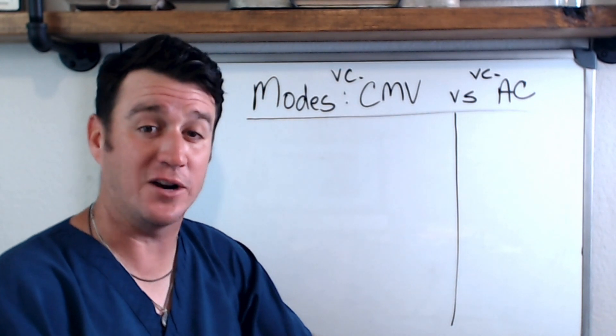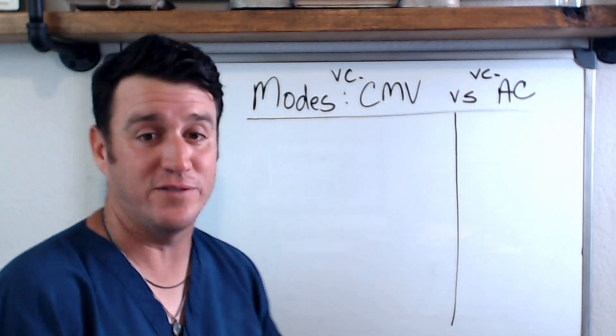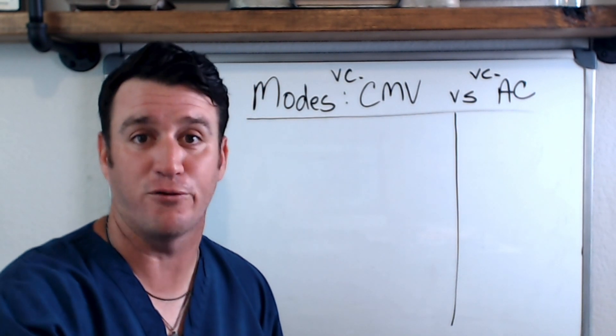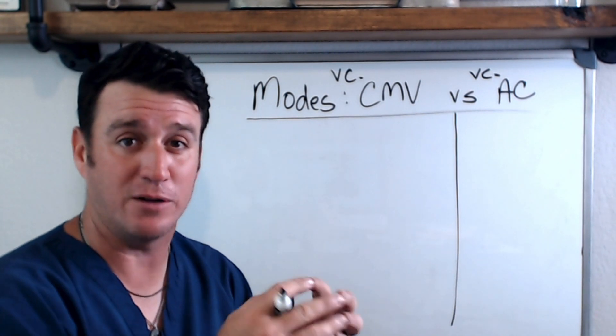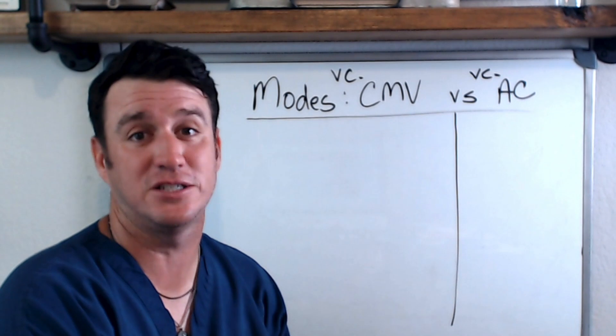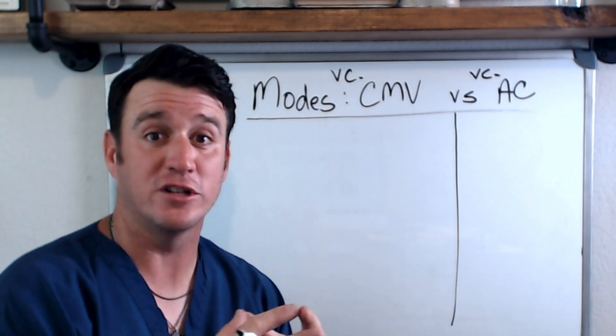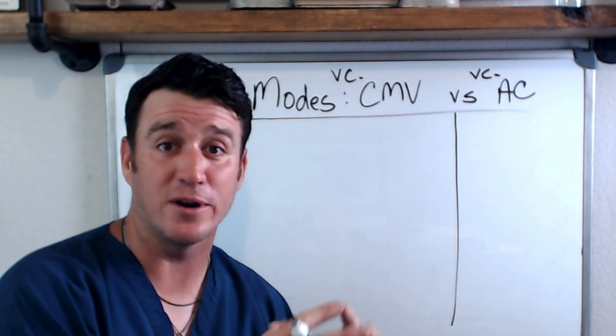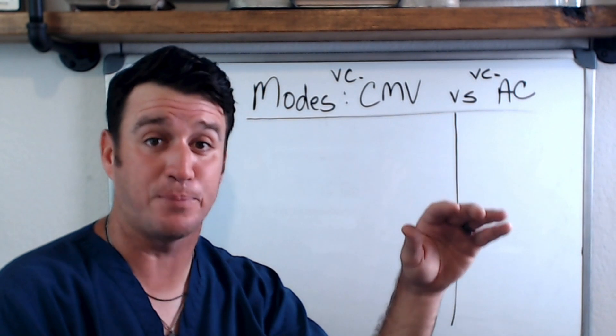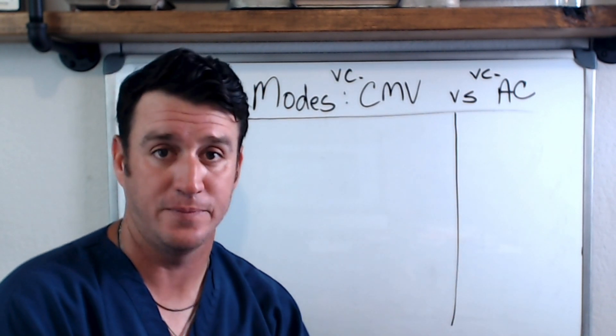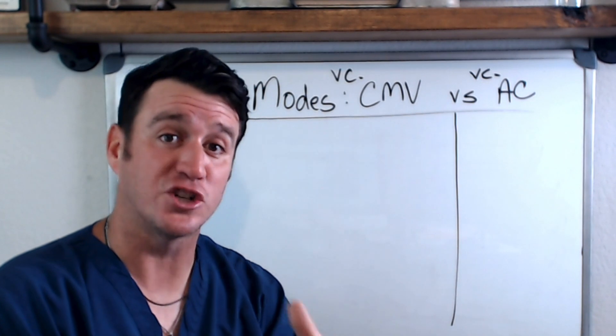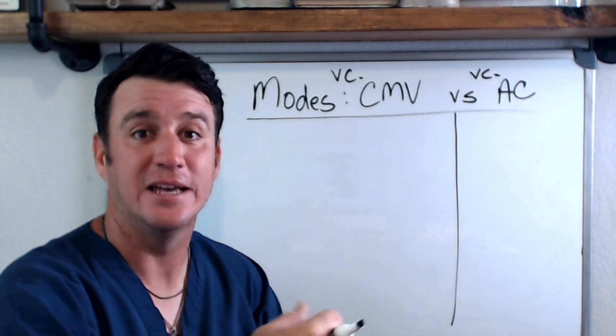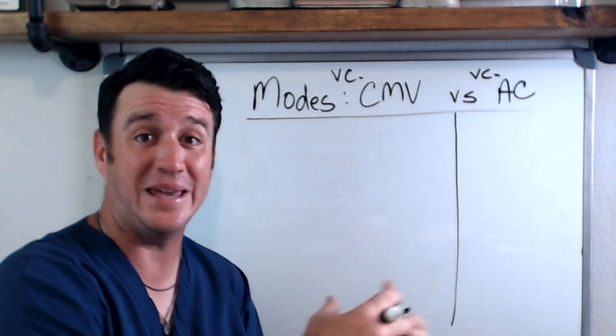You may notice a 'VC' in front of these two modes of mechanical ventilation. That's there to illustrate that in this first segment, when we're talking about settings, we're going to be operating in volume control. When you're in volume control, you set parameters that control delivered volume, but pressure will vary.